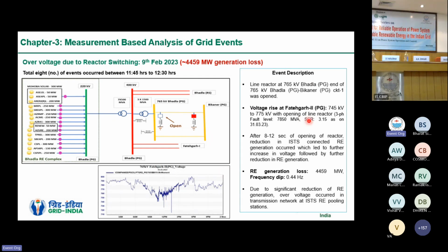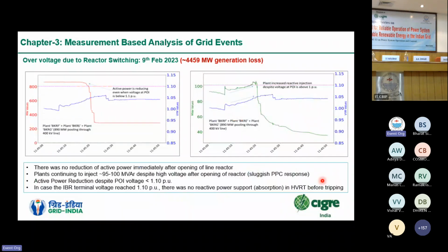On opening of the line reactor, the voltage went from 745 kV to 775 kV. This voltage was not near the HVRT threshold, and there was no immediate generation loss. But after 8 to 12 seconds of opening of this reactor, we saw a gradual rise in voltage, and subsequently the RE generation also reduced, and there was a loss of around 4,500 megawatt generation. So what actually resulted in the gradual rise in voltage after opening of this reactor, and the ultimate tripping of this large quantum of generation?